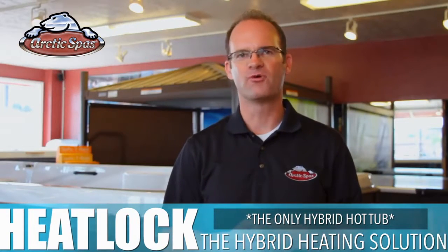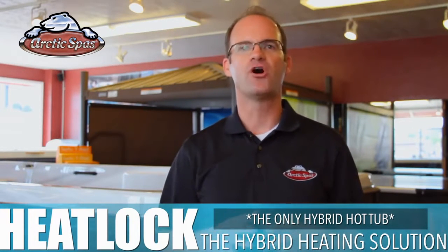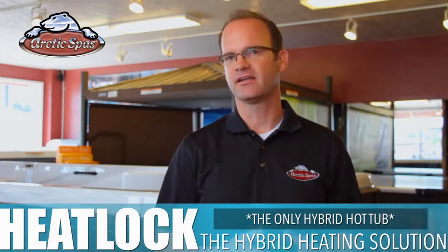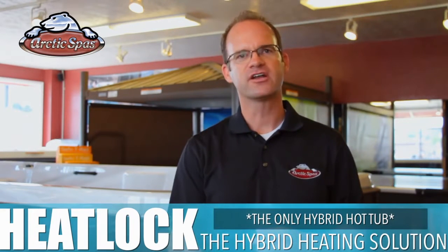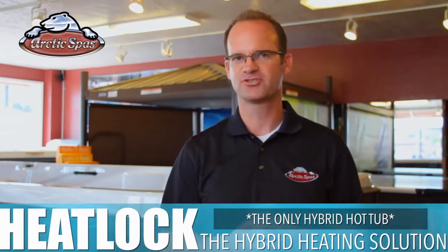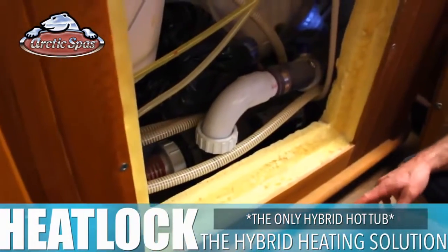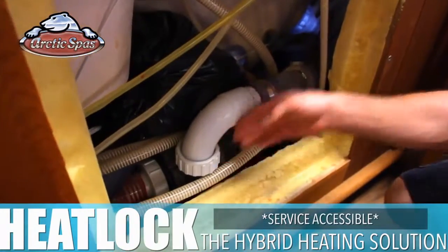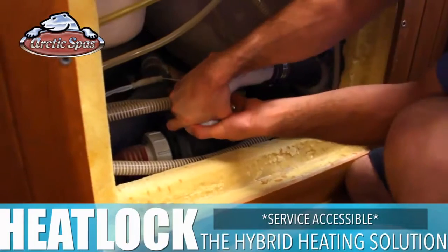Lastly, Arctic Spas have one more advantage that is often overlooked. Way back in 1989, I started out servicing all brands of hot tubs. Whenever there was a leak in another brand, I had to find the leak by taking apart the cabinet and digging out the wet foam until I found the source of the leak. With an Arctic Spa, it's a service tech's dream come true. Since the foam is sprayed on the cabinet instead of the plumbing, when you open up the access door, what you see is nothing more than naked plumbing. To find and fix a leak on an Arctic Spa, all you do is open the door and look for a leak. This saves hours of labor and lots of your money when you're paying for the repair.